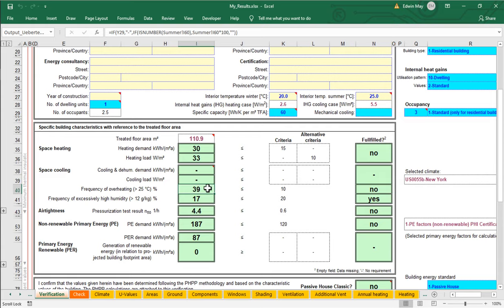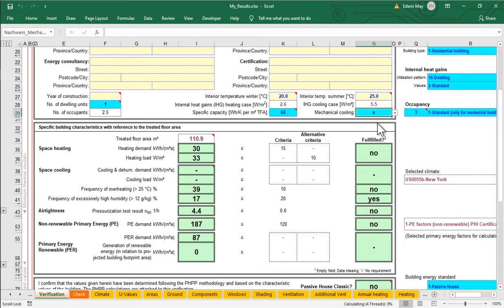The reason we're not getting any information here on the energy used for our air conditioning system is that we don't have an air conditioning system, which is why we have such high overheating and over-humidity in our project. So how are we going to turn on mechanical cooling? Let's say we're working in a place like New York where we cannot get away with passive cooling — we're going to have to use some sort of active air conditioning and dehumidification system. It's quite straightforward: all we need to do is come up here to mechanical cooling, and instead of leaving it blank, we just check it with an X. Notice all of a sudden now, cooling and dehumidification demand and peak cooling loads are getting calculated. Notice my frequency of overheating zeroes out, because if you have an air conditioning system that's properly sized, you should be able to manage that cooling energy demand.